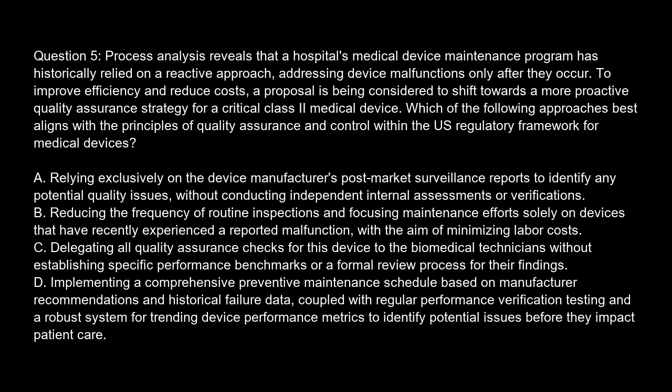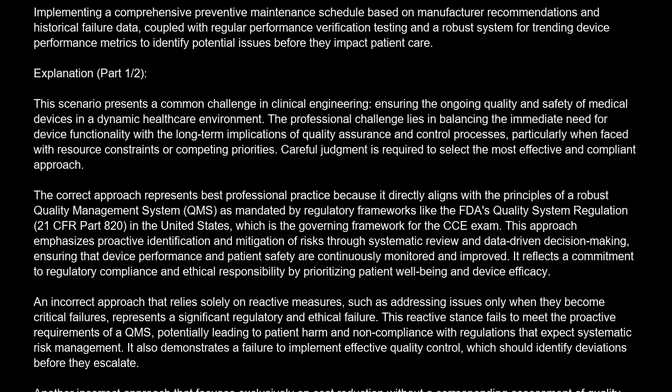Option C. Delegating all quality assurance checks for this device to the biomedical technicians, without establishing specific performance benchmarks or a formal review process for their findings. Option D. Implementing a comprehensive preventive maintenance schedule based on manufacturer recommendations and historical failure data, coupled with regular performance verification testing, and a robust system for trending device performance metrics to identify potential issues before they impact patient care. The correct answer is D.